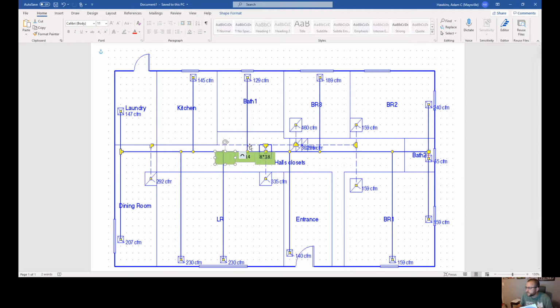All right, so the next piece. After that first 8 by 14, which had to carry everything on this end, in this bathroom we said we took out 50 CFM. I know it says 129, but we said it was 50. So how much do we have left? We had 550 going to the left. We took off 50. We have 500 left. All right, so now go to your ductulator, 0.1 at 500.